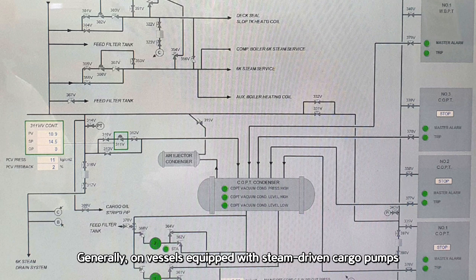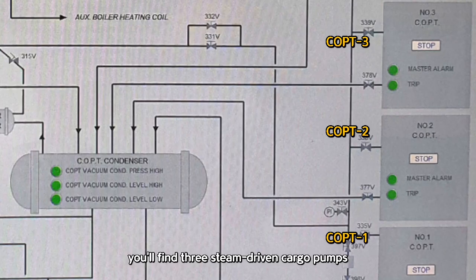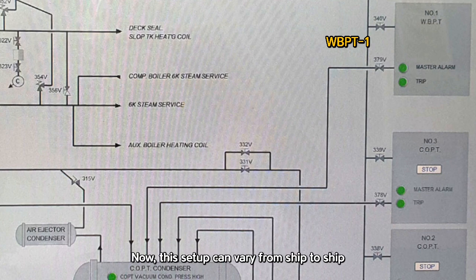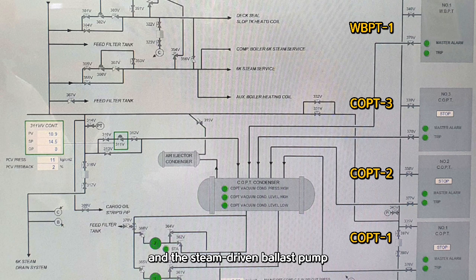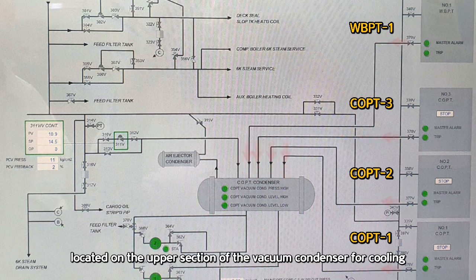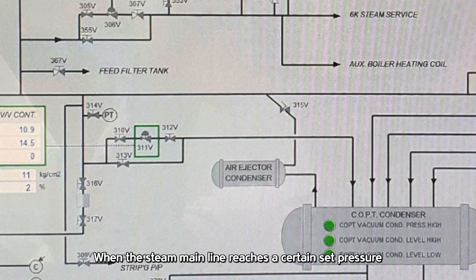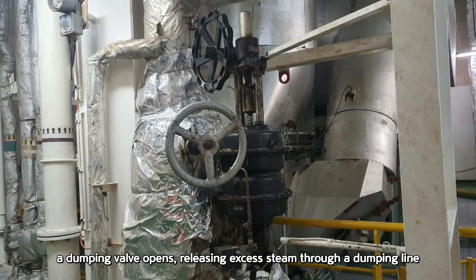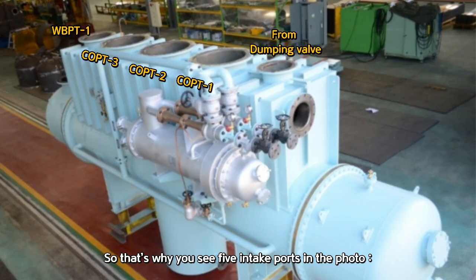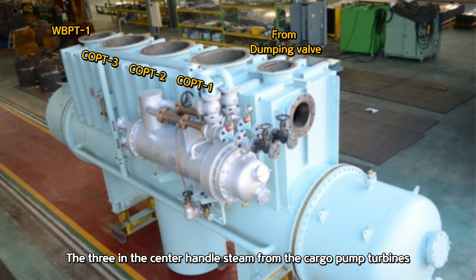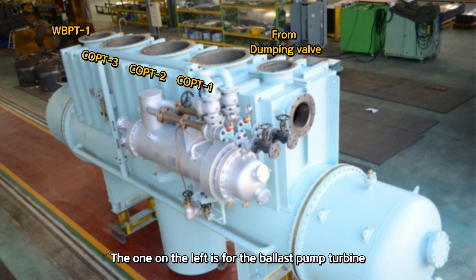Generally, on vessels equipped with steam-driven cargo pumps, you'll find three steam-driven cargo pumps and two ballast pumps. Now, this setup can vary from ship to ship, but typically, one of the ballast pumps is electric motor-driven, while the other is steam-driven. So the three cargo pump turbines and the steam-driven ballast pump all discharge high-pressure, high-velocity steam. This steam is directed into four of the intake ports, located on the upper section of the vacuum condenser, for cooling. As for the fifth hole, it serves a different purpose. When the steam main line reaches a certain set pressure, a dumping valve opens, releasing excess steam through a dumping line. That steam is also handled by the condenser through the fifth intake port. So that's why you see five intake ports in the photo.